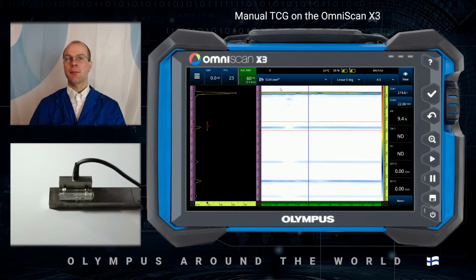I have here a setup with a 64-element linear phased array probe, a 0-degree L-wave wedge, and the sample which I'm using is a steel block with a thickness of 20 mm. I want to use three TCG points. The first point at the interface echo, the second point at the back wall echo, and the third point at the repeat of the back wall.